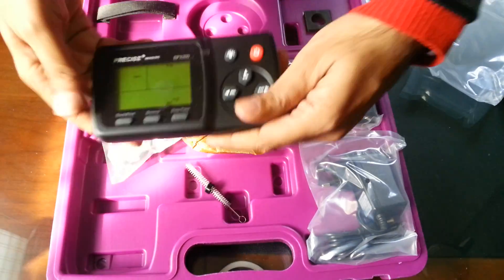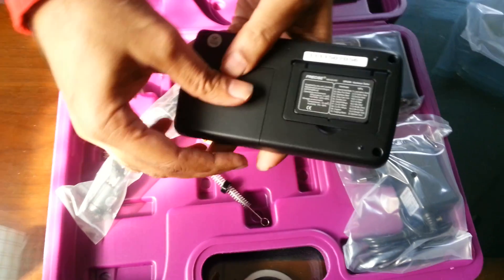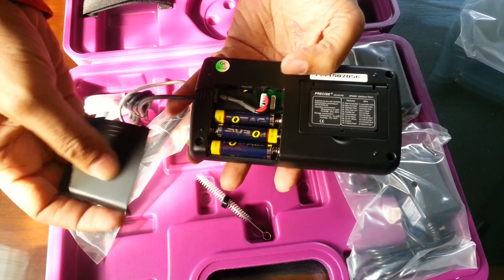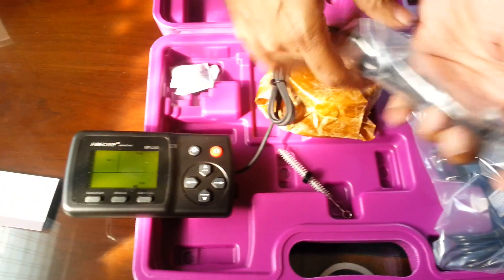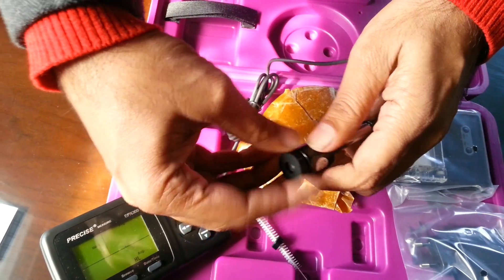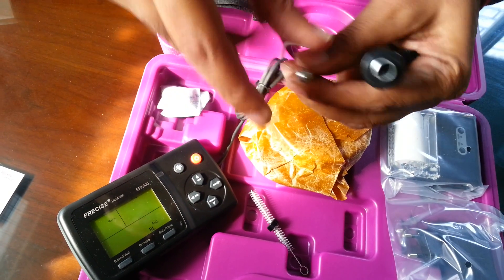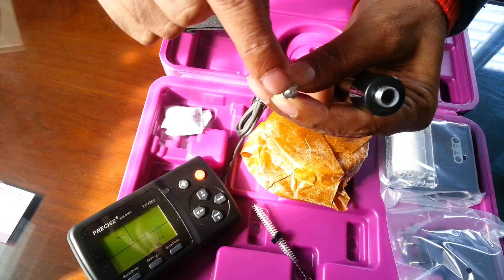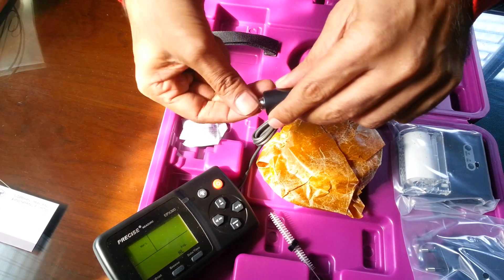This model is the EPX 300. This is the main unit, and it has three 1.5V AAA batteries — four and a half volts total. Connected to it through a cable is the D probe. The D probe is a device which takes a mechanical reading and converts it to electrical. This is the indenter, which has a ball here — a ball indenter, 1/16th of an inch.